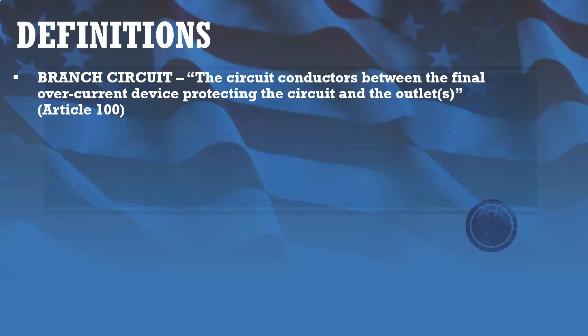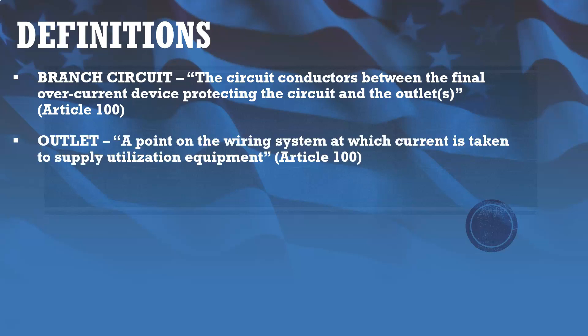Definitions. A branch circuit is the circuit conductors between the final overcurrent device protecting the circuit and the outlets. An example would be, in a typical residential situation, a circuit supplying receptacles or a circuit supplying light fixtures. We also have the definition of an outlet: a point on the wiring system at which current is taken to supply utilization equipment — in other words, where we're utilizing current in the circuit.